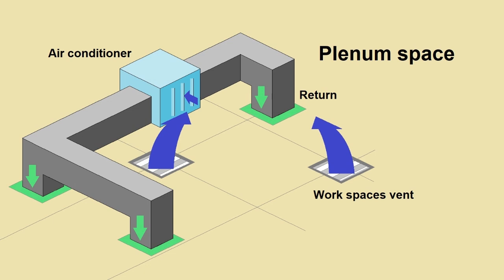It is critically important that we use only plenum rated cable in a plenum space because if there is a fire in the overhead and the cables catch on fire, it is plenum rated cable, also known as CMP, that has the qualities of both fire retardants and a special formula polyurethane outer jacket that gives off less toxic fumes if it catches on fire.